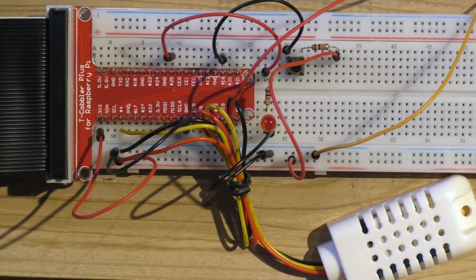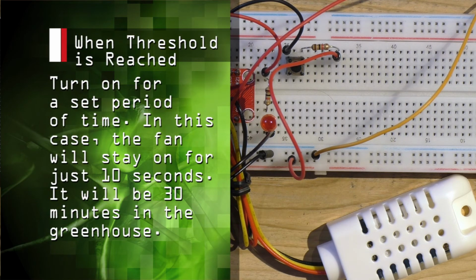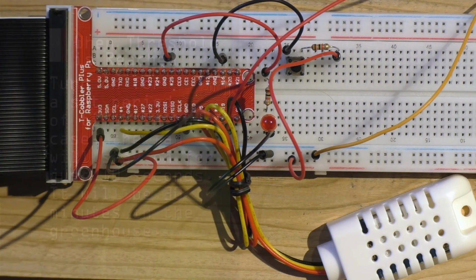So you don't want it cycling on and off frequently like that. One of the things the code needed to do was be smart enough to say, okay, we've crossed the threshold, we're at 25 degrees, let's turn the fan on, and then we'll run it for 1 hour, or we'll run it for half an hour, some period of time. And then after it's run for that hour, we're going to check the temperature again. If the temperature is still above that temperature, then we'll keep running. And if it's not, then we'll turn off and stay off until the next time it goes above that threshold.